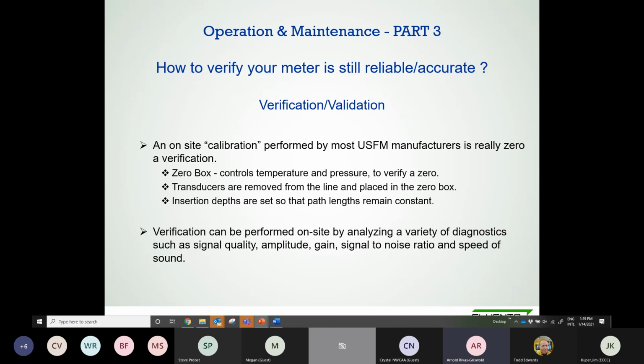So what do we do on a regular basis? The verification process, or the validation process, is just that, more than a calibration. It's just verifying on a yearly basis, say, or maybe, if you determine based on the process conditions, as I mentioned before, that you have to go on a more frequent basis.